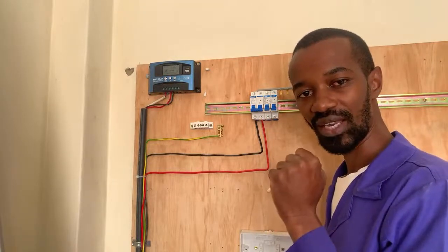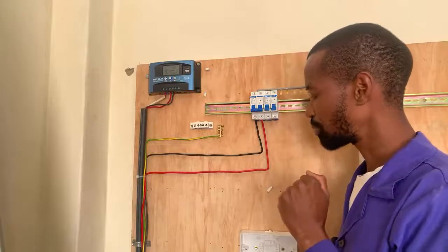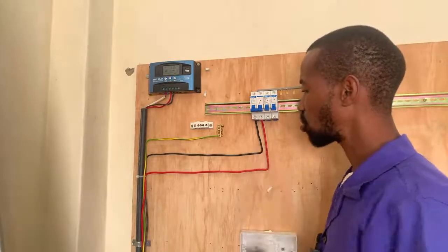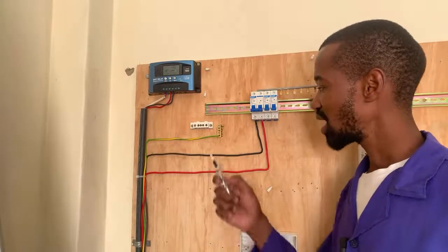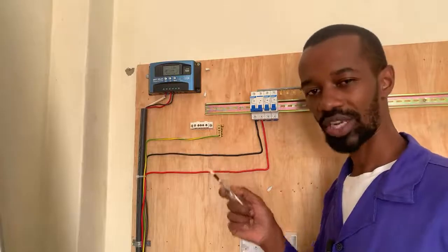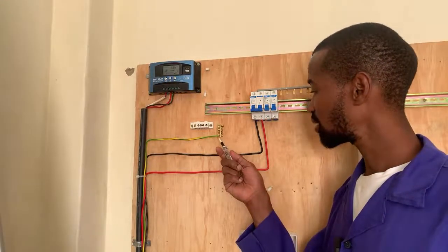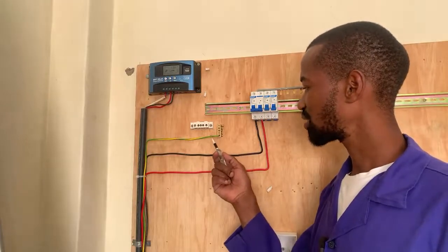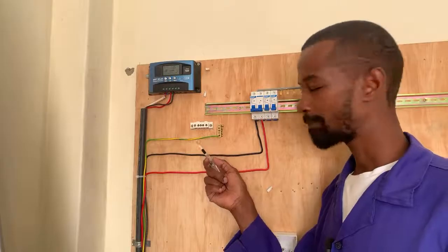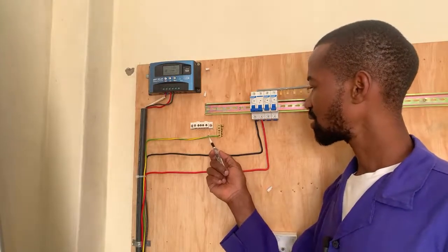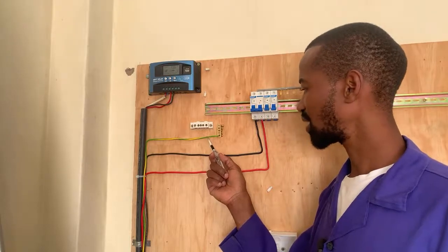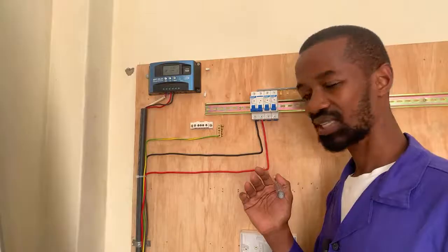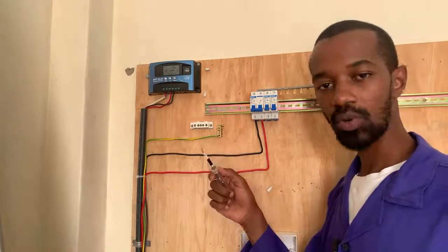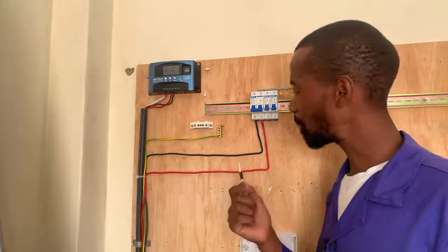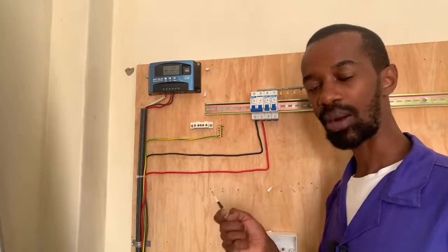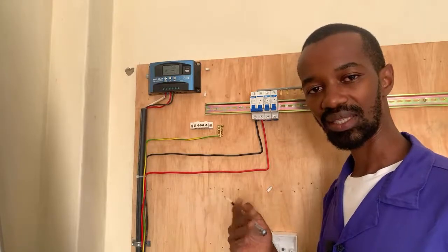The neutral is very important in any electrical installation. In some places the neutral has been disconnected, and then someone decides to tap at the earth connection instead. That is very wrong, because if there's a loose connection or failure on the earthing, since earth connections often fail, you will get a spike in voltage. This spike is commonly referred to as a power surge, which ends up damaging appliances at home.